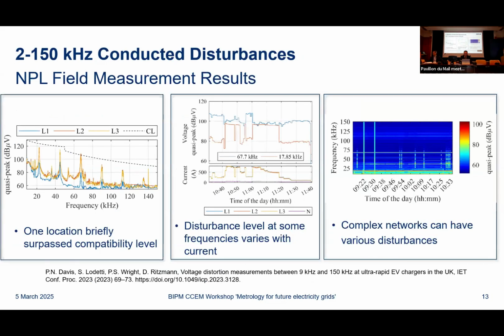And so I'm just going to show some sample results. There's actually a conference paper that you can look up to read a bit more about it. But on the left-hand side, for example, what you can see is the spectrum that resulted from using the CISPR-16 quasi-peak value from one of the locations. And you can see these peaks, and they are associated with what we believe is the switching frequency of those EV chargers. We think it's usually the first one, around 22.5 kilohertz in this case, and then you can see the harmonics of this switching frequency.